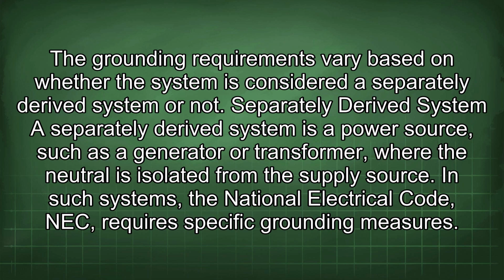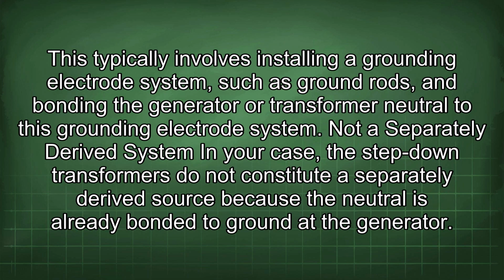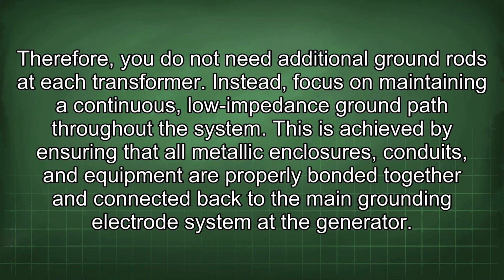In such systems, the National Electrical Code (NEC) requires specific grounding measures. This typically involves installing a grounding electrode system, such as ground rods, and bonding the generator or transformer neutral to this grounding electrode system. Not a separately derived system: in your case, the step-down transformers do not constitute a separately derived source because the neutral is already bonded to ground at the generator. Therefore, you do not need additional ground rods at each transformer.